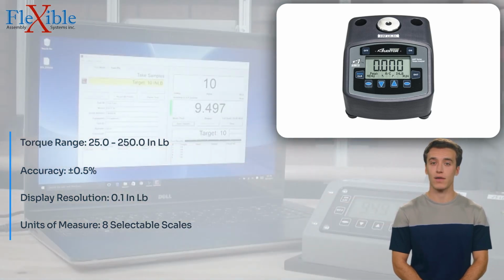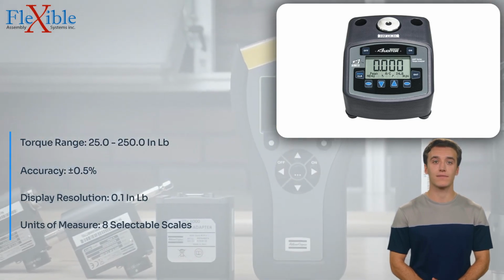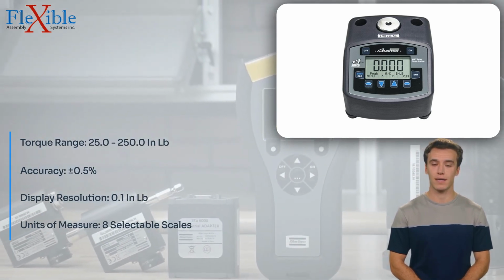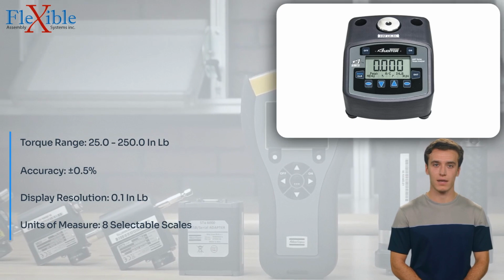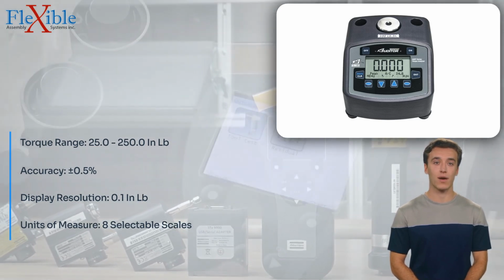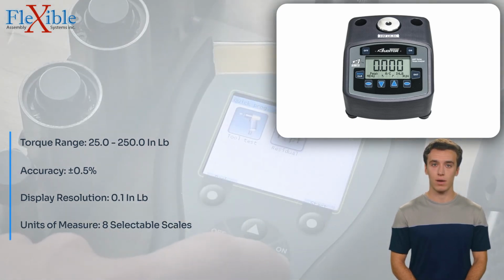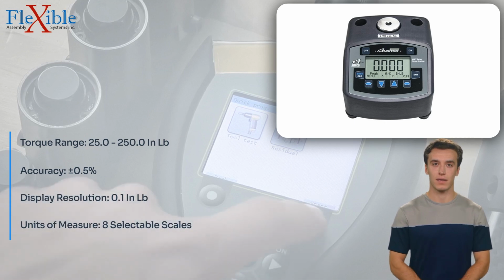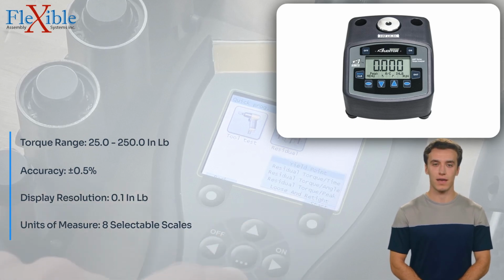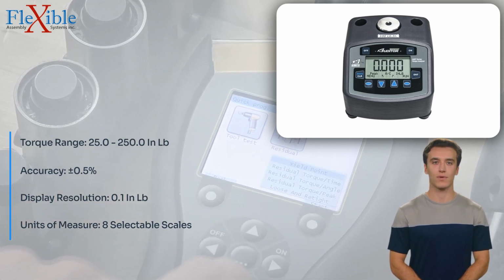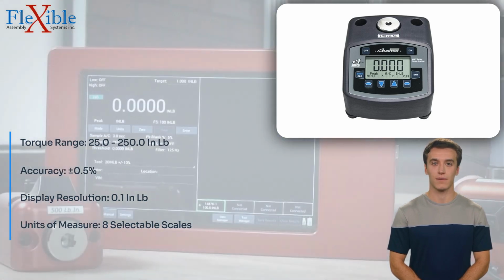The AUET-250 provides 3 processing modes for torque signals, enabling users to select the most appropriate method for their application: capture the highest torque peak, record the first torque peak, or monitor all torsional strain applied to the transducer in real time. Additionally, the pulse mode is specifically designed for testing hydraulic pulse tools, accurately recording the peak value achieved during the tool's operation.